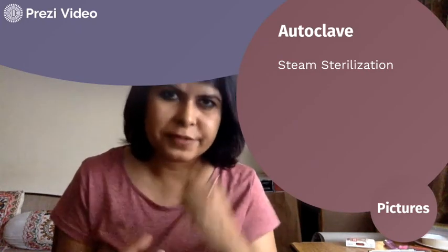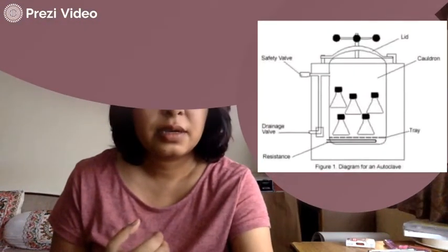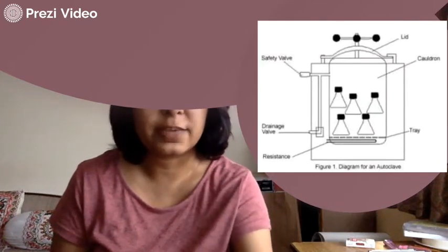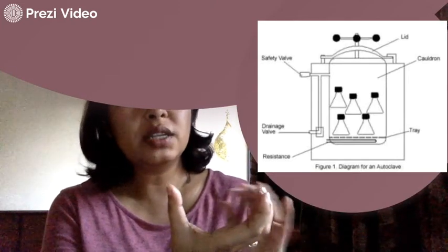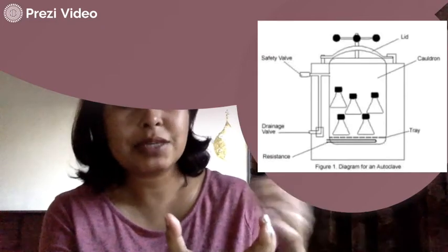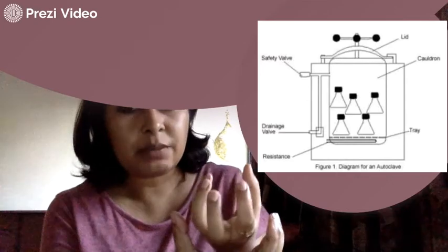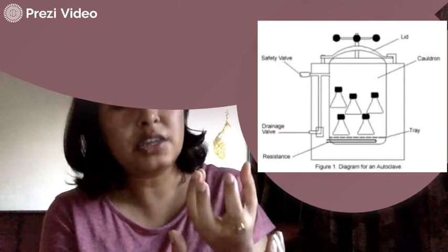What is an autoclave? An autoclave is basically a pressure cooker — with some modern and safety additives because it is going to attain a much higher pressure. Let us look at a simplified diagram of an autoclave. If you look at this instrument, the first thing you should notice is that there are two vessels or two chambers: an outer chamber and an inner chamber. The outer chamber holds the water which will ultimately get converted into steam, since this is a steam-type sterilization.